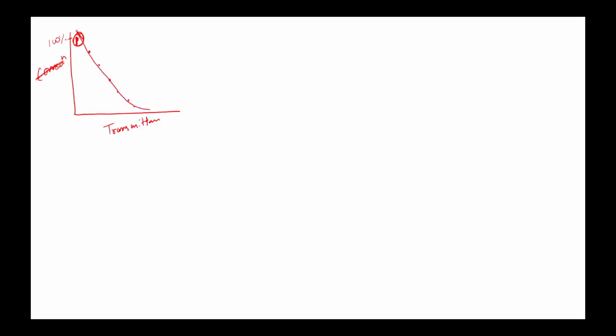Now at this condition, finding out the concentration of a higher concentration sample would be very difficult, because if we correlate with transmittance, it will be very low. If the concentration is high, the transmittance will be very low, at the very bottom of the graph. So if we calculate the concentration of the sample based on transmittance, it would be very difficult.